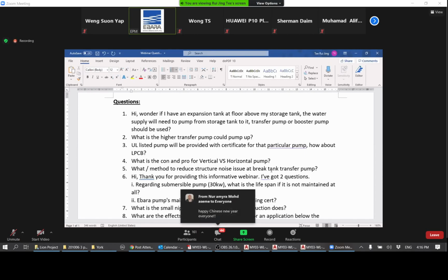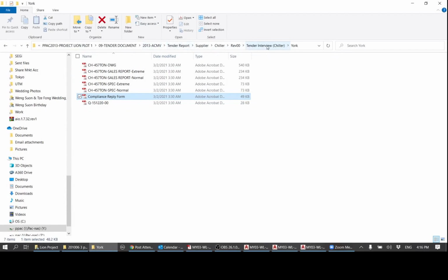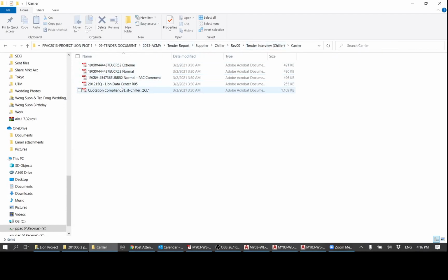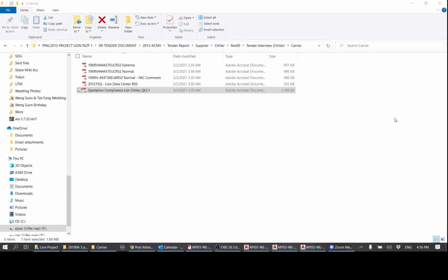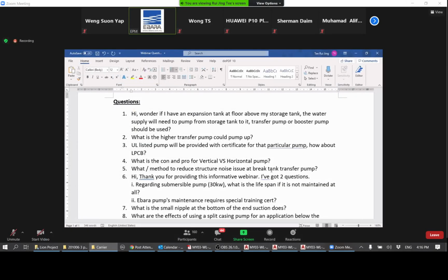Secondly, a vertical pump in most cases does not need any alignment because of the vertical shaft, compared to a horizontal pump, for example, like a horizontal split case or end suction pump, where the motor and the pump are two separate shafts joined in the middle by a coupling. So when the motor is spinning at, let's say, 2,900 RPM or even 1,500 RPM, the shafts have to be aligned to each other, the pump shaft and the motor shaft, or else even if it is 1 degree off alignment, then you will start to have misalignment issues like vibration, noise, and so on.